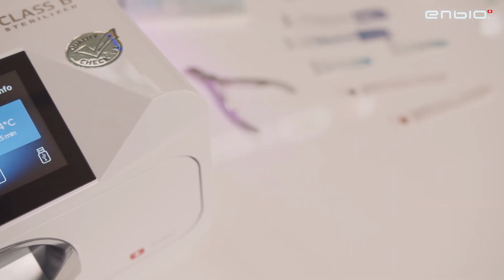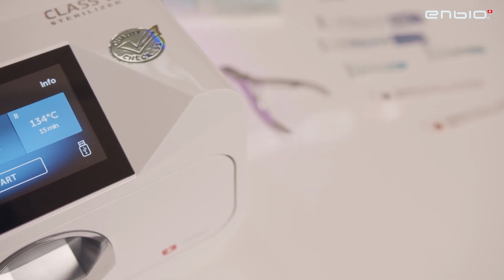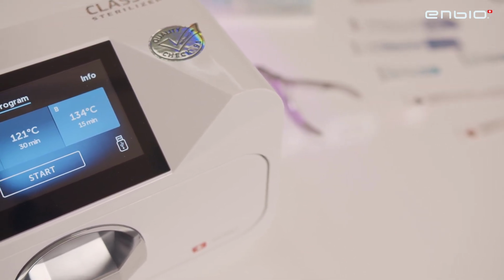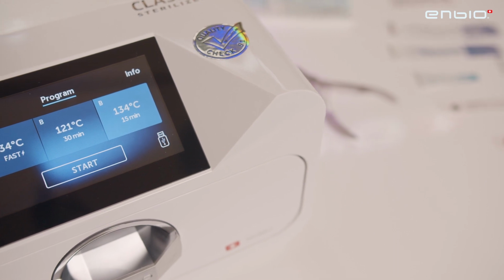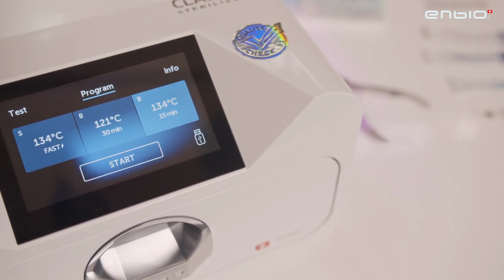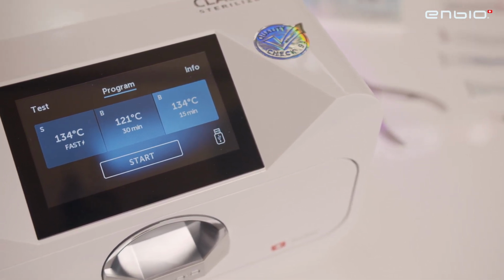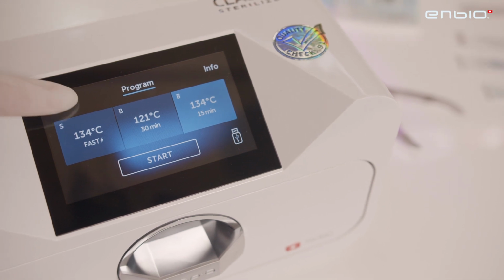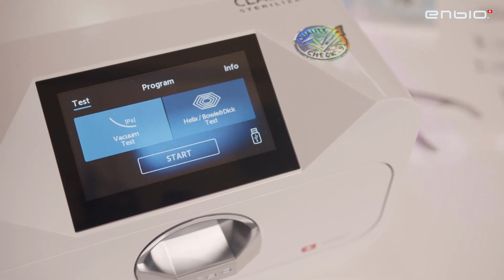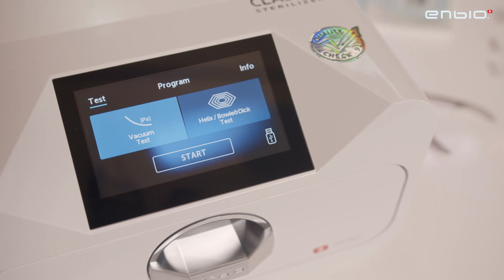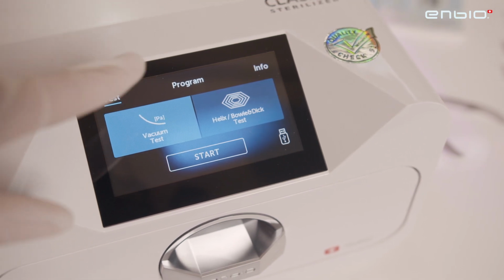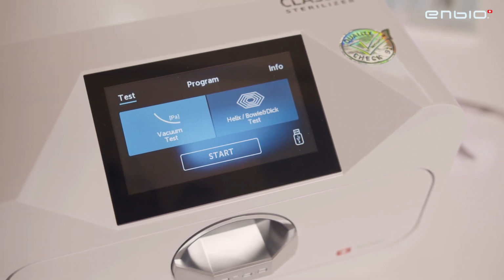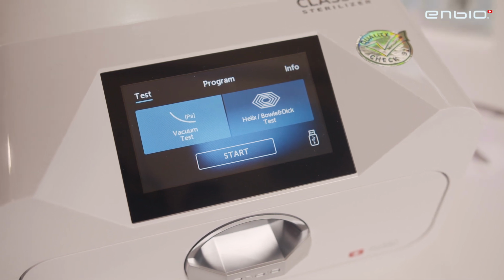Another test that we can perform is the vacuum test, which shows if the vacuum is functioning properly during the sterilization process. In order to perform this test, we need to select it from the test menu on the autoclave. So for instance, we click on test, and here we can see the vacuum test. And we just click on it, and then we click on start, and the test is going to be performed.